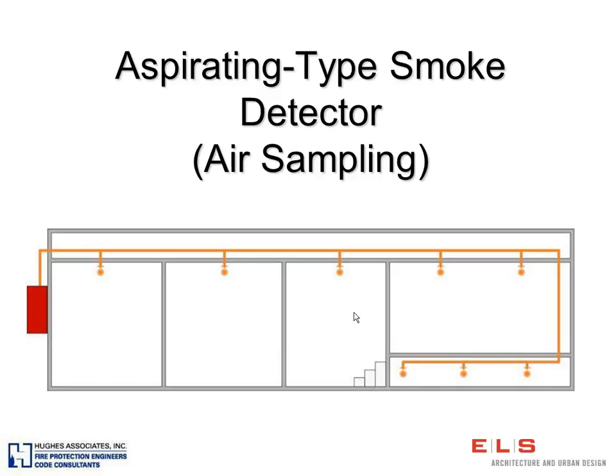Another type of smoke detector, which I think is a very appropriate application in the protection of historic buildings, would be an aspirating type smoke detector, or air sampling. If we were to talk about Kleenex or tissues, when I use this term, aspirating type smoke detector, I'm talking about the tissue. The name that a lot of people associate with this type of system is VESDA, but that is a brand name. It stands for Very Early Smoke Detection Apparatus, and this is the generic term for it.